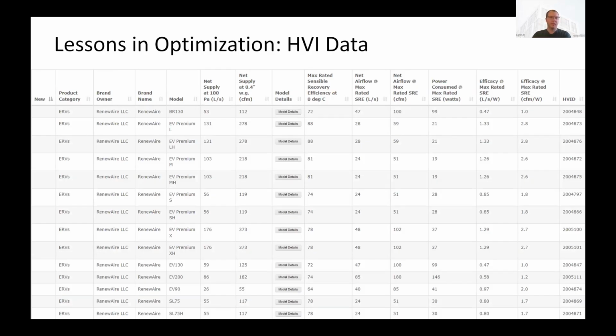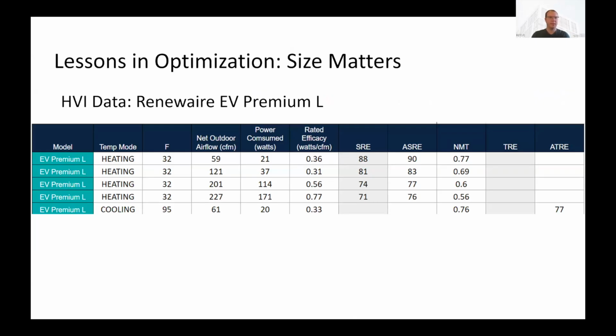When we talk about data, PHIUS likes to use the HVI data, and it's very useful for a few reasons. We're going to go through a lot of examples here. But the data that you can get out of HVI is at multiple airflow rates. The example here is a Renewaire EV Premium L model. When we look at the net outdoor airflow, we can see it starts at 59 CFM, and goes up to 121, 201, 227, and that's all heating, and then there's also one line for cooling. As airflow increases, we can see how that affects the other pieces of data here.